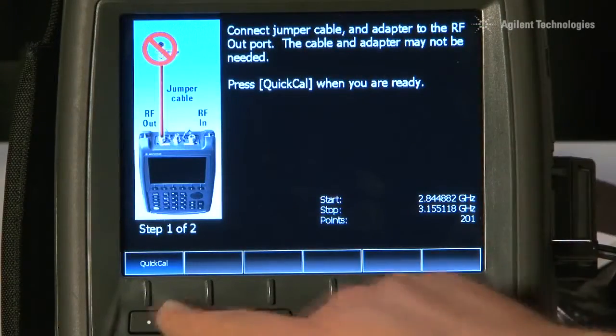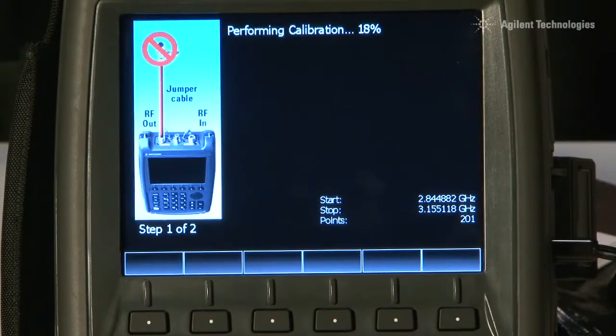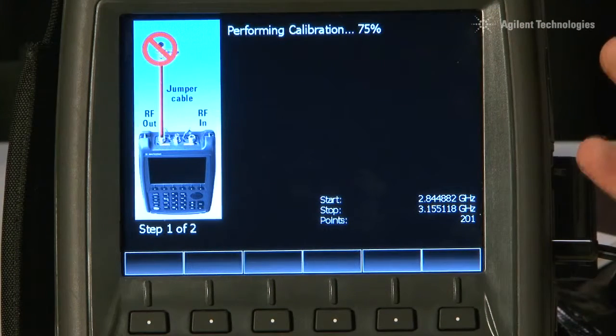Best of all, the built-in quick-cal capability means that we can calibrate the instrument when out on site without the need for an external open-short-load calibration kit.